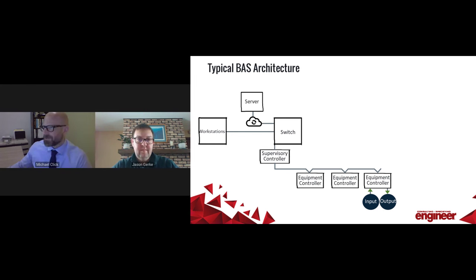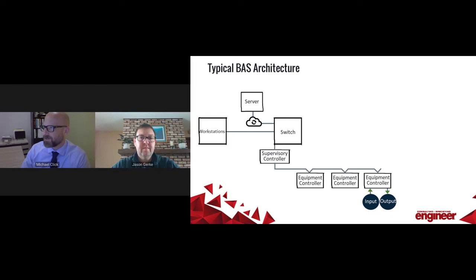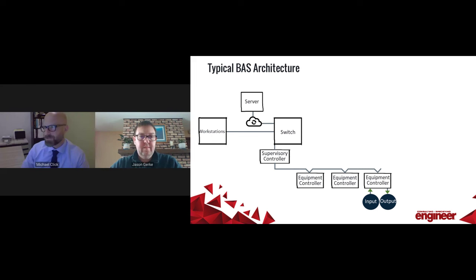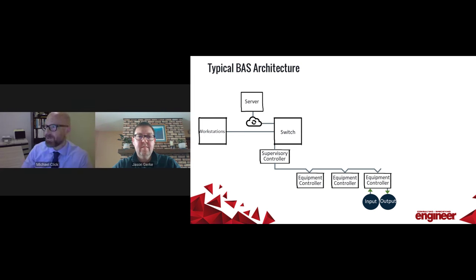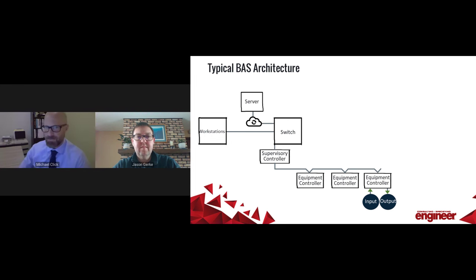Taking a deeper look into building automation architecture: there are really four layers to any modern building automation system architecture. There's your server application level, then your supervisory layer called supervisory control, your field control layer which is the equipment controllers tied to the bus, and then your input-output layer — your I/O.